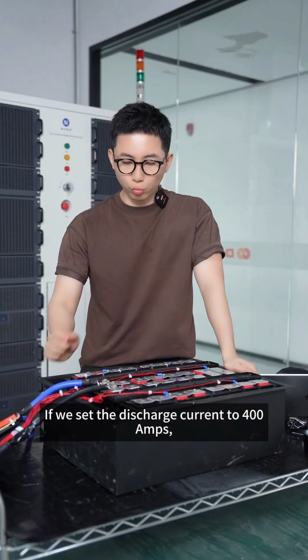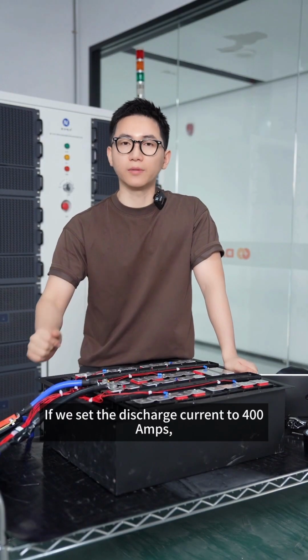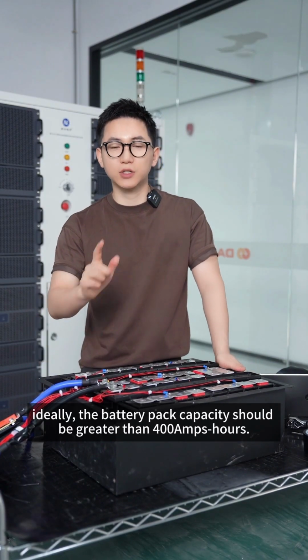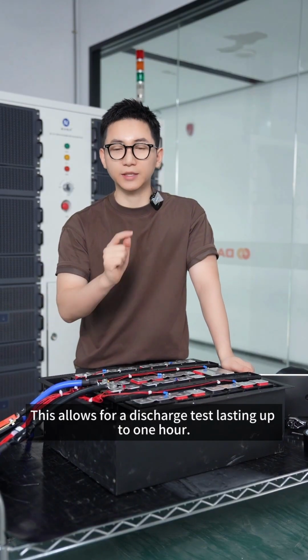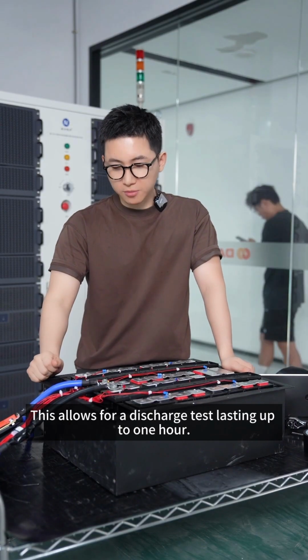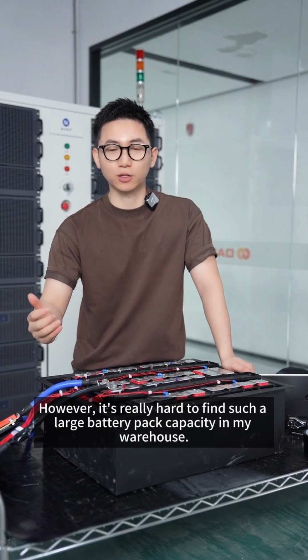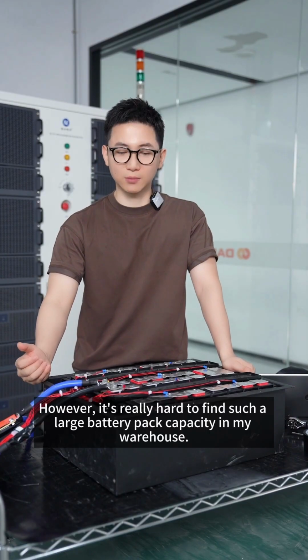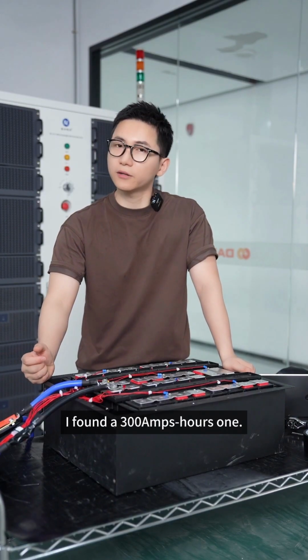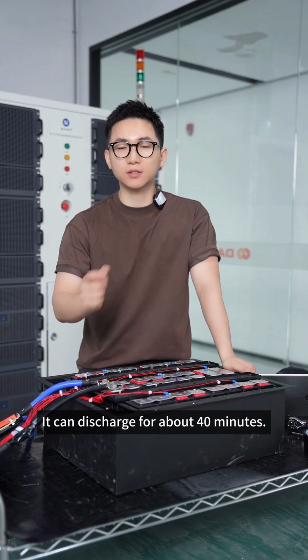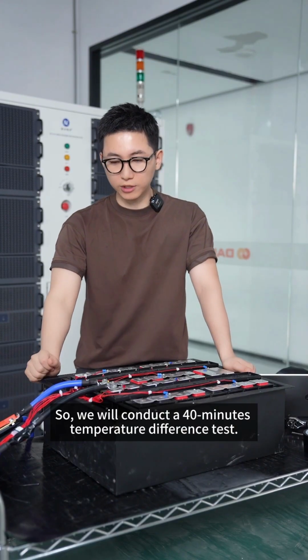Let's start. If we set the discharge current to 400 amps, ideally, the battery pack capacity should be greater than 400 amps hours. This allows for a discharge test lasting up to 1 hour. However, it's really hard to find such a large battery pack capacity in my warehouse. I found a 300 amps hours one. It can discharge for about 40 minutes. So we will conduct a 40 minutes temperature difference test.